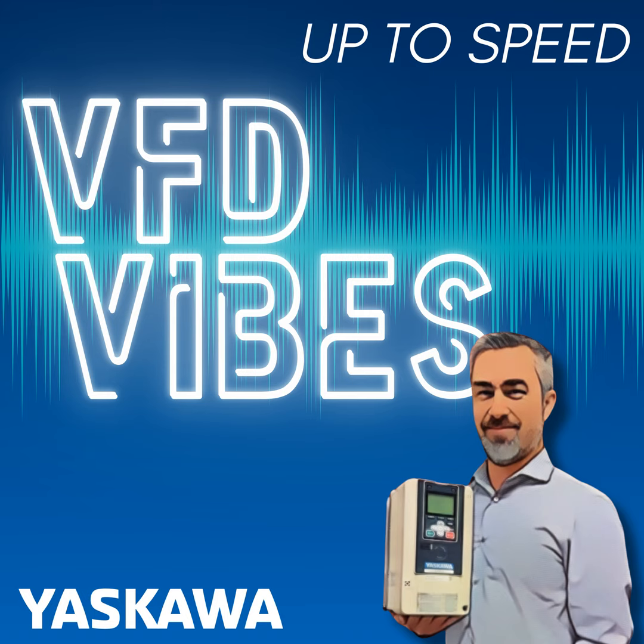So again, when we talk about optimizing the drive efficiency for the application, that V by F pattern is, well, one, we're avoiding a fault condition, but we're actually, once again, optimizing to get the most efficiency for the application that we're running. Yeah, most torque per amp. Great. What about drive overcurrent situations? Yeah, that's another one that you might see.